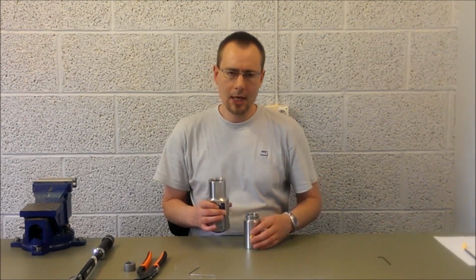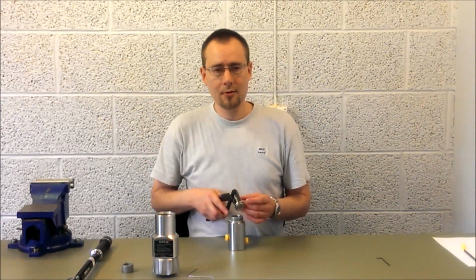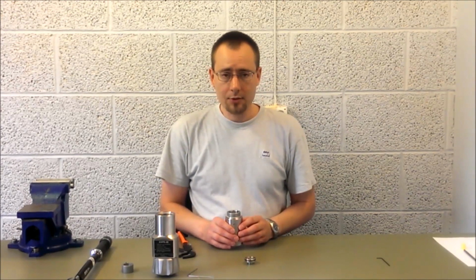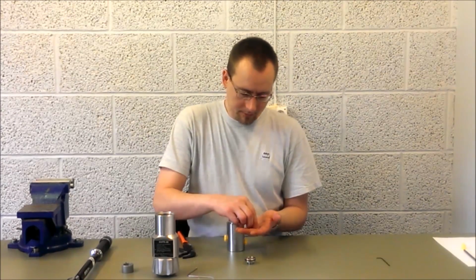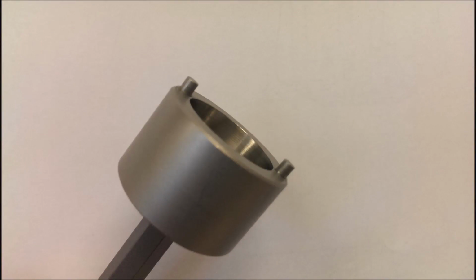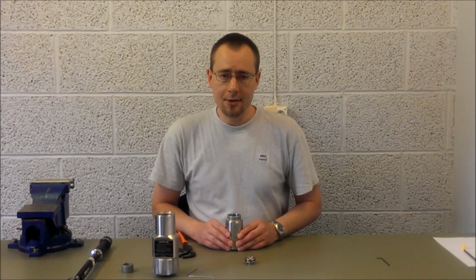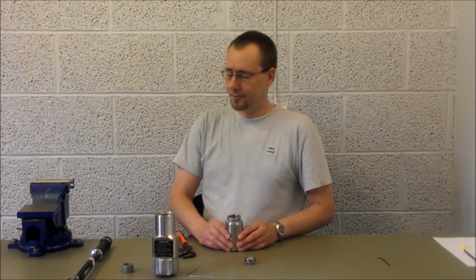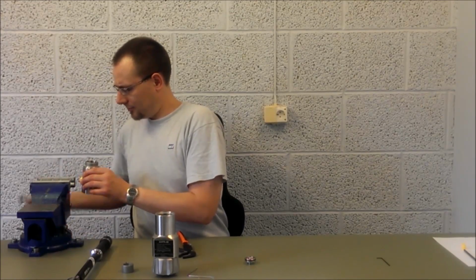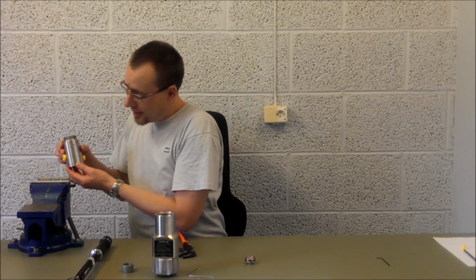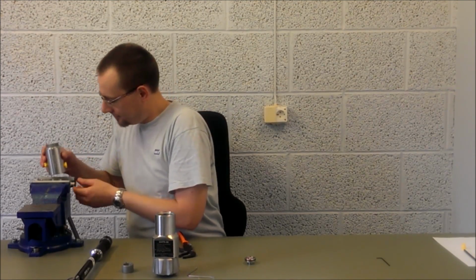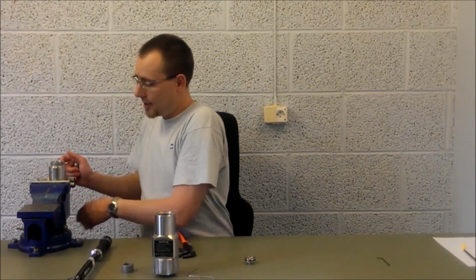Now we have separated the low pressure housing and the high pressure housing. Remove the piston with the O-ring. Also remove the metal ball. To unscrew the pressure sensor, you need to fixate the housing. Make sure that the inlet and outlet ports and the engravement remain unharmed. A good pair of aluminum V-blocks is recommended.